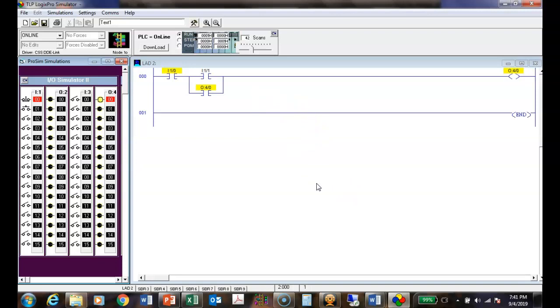Well, look, this is a normally closed push button. So when I start it up, it says it's true. I just press the stop button, right? I guess I should have given that a name. Notice, you say that's a normally open contact, it's not. I got it hooked up to a normally closed switch, so it's true all the time, right? Y'all see that? See, it's yellow, it's true all the time, because I got it hooked to a normally closed switch. And this really gets people in motor controls messed up.